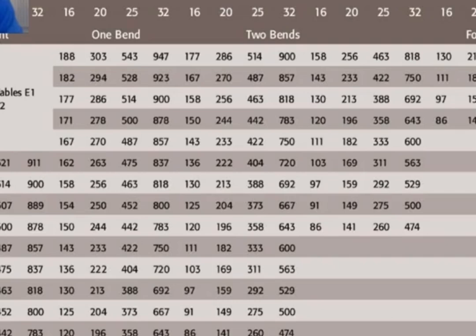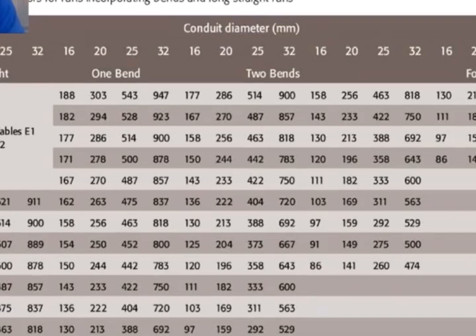So it gives me a multiplier of 1.4 for 38mm, 2.6 if I want 50mm, or 4.2 for 63mm. These are fairly big conduits, which is why they're not in the table. I've never installed anything to that size, but it could possibly happen. All right, so that's what we're using when we're not doing short straight runs.